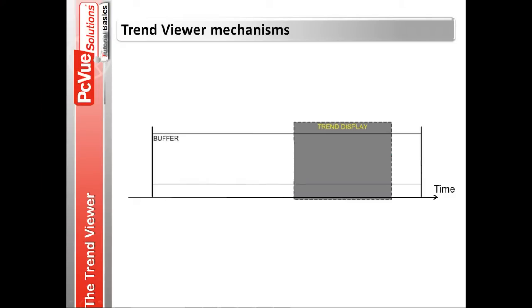Each trend viewer contains a configurable display buffer where the values for each trace are stored. When the mimic opens, the buffer is empty and starts to fill with the real-time points. When the mimic is closed, the buffer is emptied unless the mimic has the property cache enabled.